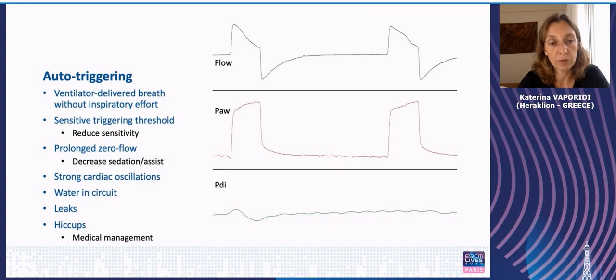Strong cardiac oscillations, again in the setting of prolonged zero flow, may trigger the ventilator, as does water in the circuit or leaks, which can be managed, obviously, by fixing the cause. Hiccups is a condition that causes very large swings in esophageal pressure and obviously cannot be managed by modulating the triggering threshold, but requires medical management.